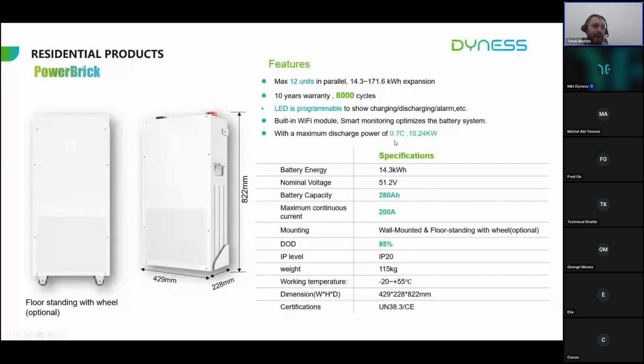Also, I want to add a note here. Most manufacturers in this size, in 15 kilowatt hour, have a discharge rate of 0.3 C, not 0.7 C. So we have many advantages in this product that will be launched soon. The DOD, for sure, as all of our batteries, can reach 95%. The weight also is competitive compared to other manufacturers, it's 115 kilogram.